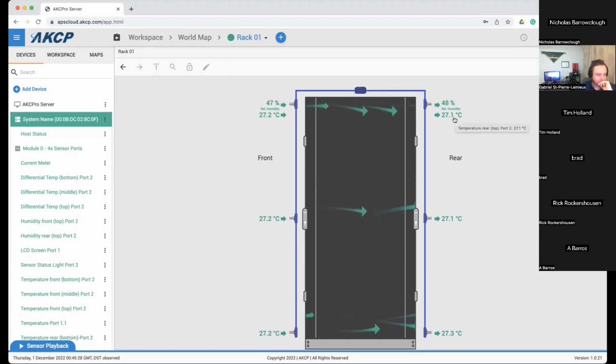It's basically the same. In a data center, you'd expect to see temperature at the front, say around 24, 25 degrees, and temperature at the rear of 36, 37, up to 40 degrees, depending on how much heat and how much work the servers inside of the rack are doing. So this data becomes the plugin to the sensorCFD model. Rather than just saying the temperature coming into this rack should be 24 degrees and the temperature coming out should be 37, we'll get real live sensor data.